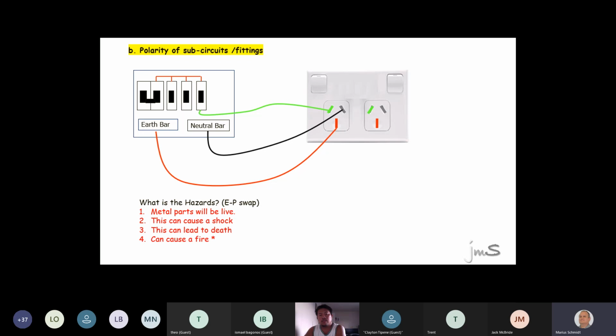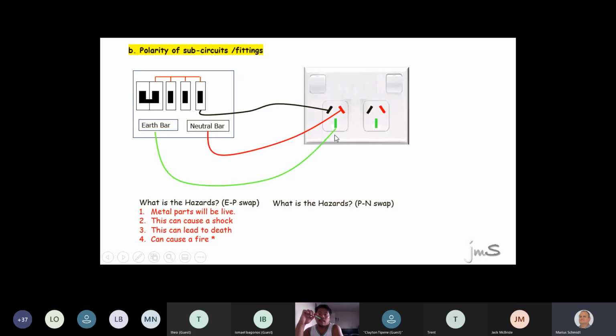So they can ask you scenario questions. Now, guys, that is if phase and earth are swapped. What about if phase and neutral are swapped? If I swap phase and neutral around, see there, phase and neutral are swapped. Will the appliance still work? Which conductor do we switch now? The neutral, right? If you swap the neutral, do you agree that the inside part is still live? Yeah, but okay, this is just an example. I should have put the link in, but you're right, 100% right.